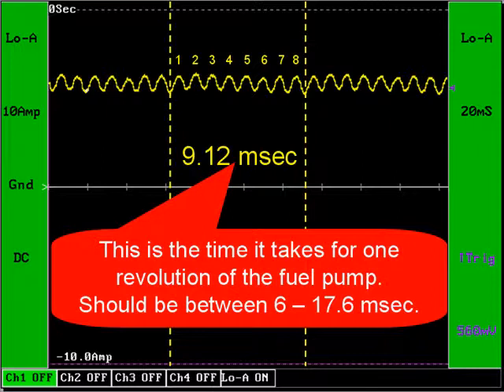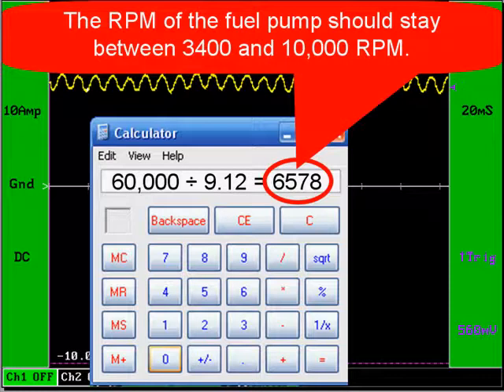The time in our example is 9.12 milliseconds, and it should not exceed 17.6 milliseconds. It shouldn't be less than 6 milliseconds. So what we're saying is the speed of the pump in milliseconds, the time it takes for a pump to do one revolution, should be between 6 and 17.6 milliseconds. And what we're saying a different way is that the pump's RPM should stay between 3,400 and 10,000 RPM.